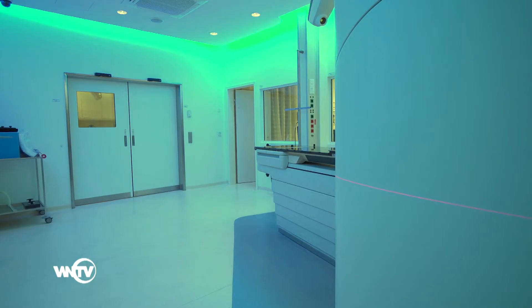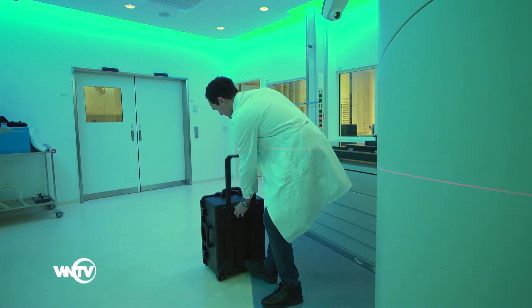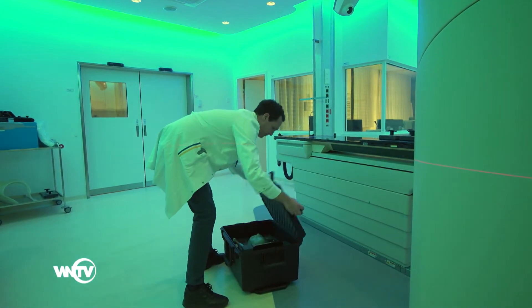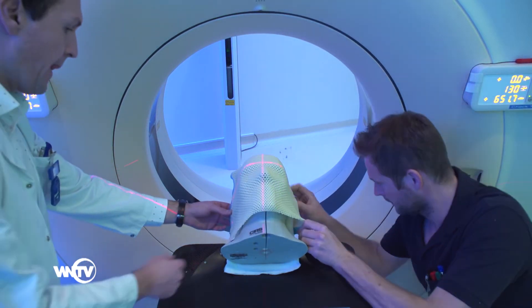As for real patients, CT imaging of the immobilized phantom is performed in order to calculate a treatment plan. The immobilization of the phantom follows the local procedure of the audited institution and is performed by the staff of the audited centre. The CT scan for the head phantom is acquired with predefined scan protocols used at the centre for cranial treatments. The CT images are then exported from the CT console to the treatment planning system.